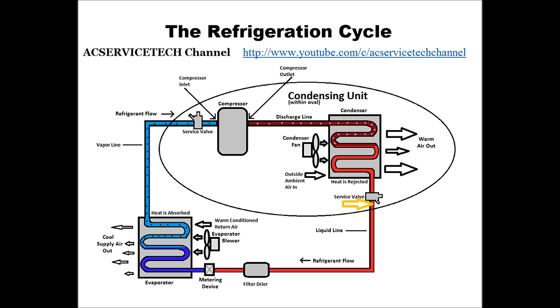Subcooling is used to check the refrigerant charge of a system with a thermostatic expansion valve. You're actually measuring a temperature decrease in liquid right at the service valve of the outdoor unit. This not only gives you the temperature decrease in liquid form, but it's also giving you a certain amount of volume of liquid to make sure that you have a steady column of liquid going to the thermostatic expansion valve.